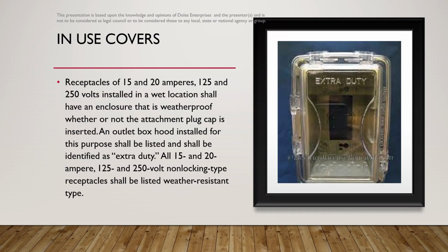Receptacles of 15 and 20 amp, 125 and 250 volts installed in a wet location shall have an enclosure that is weatherproof whether or not the attachment plug cap is inserted. An outlet box hood installed for the purpose shall be listed and shall be identified as extra duty. All 15 and 20 amp, 125, 250 volt non-locking type receptacles shall be listed weather resistant type.